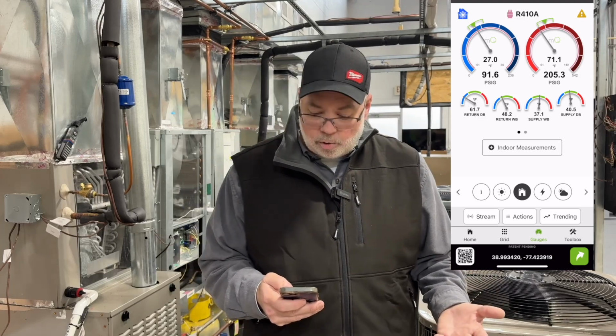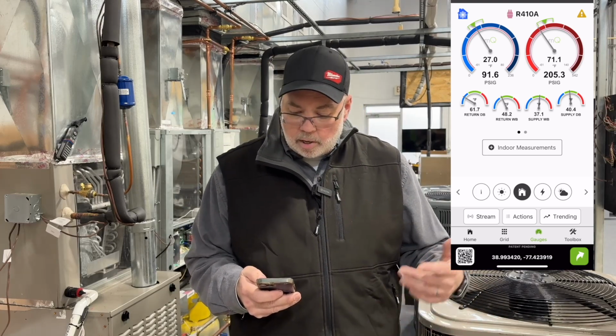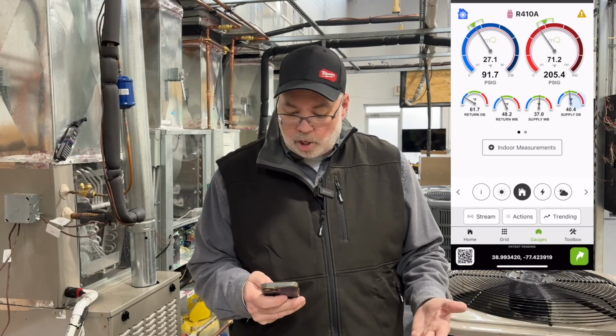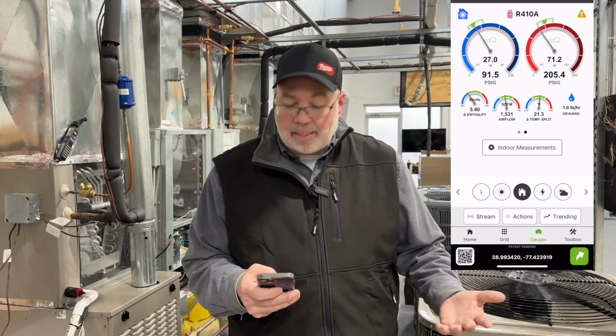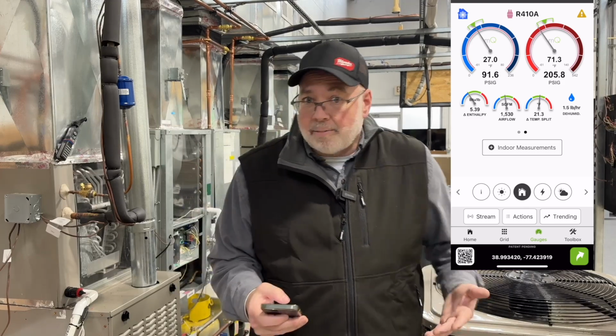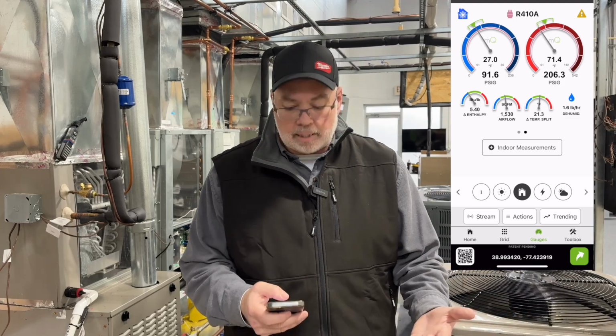Now we see our indoor information, return and supply, both dry bulb and wet bulb. We see the calculated CFM based on the enthalpy change across the evaporator coil. This is something that the JB Go V2 app does not do.